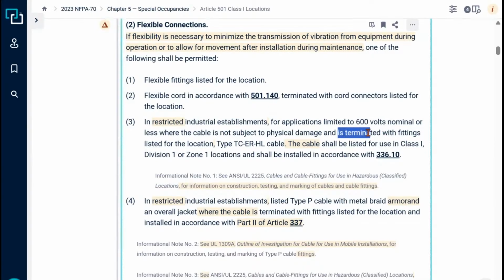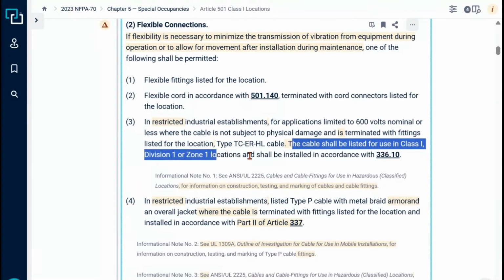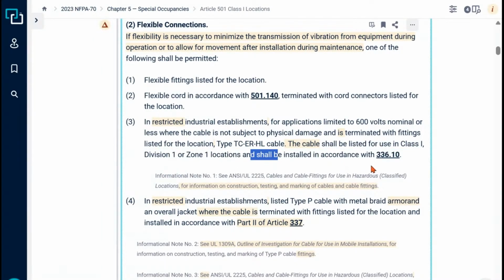It is terminated with fittings listed for the location. So in a restricted industrial establishment where I need flexibility, I'm going to be allowed to use the TC-ER-HL cable for that flexibility, provided that the fittings are listed for that location. And it says the cables shall be listed for use in Class 1 Division 1 or Zone 1 locations and shall be installed in accordance with 336.10.